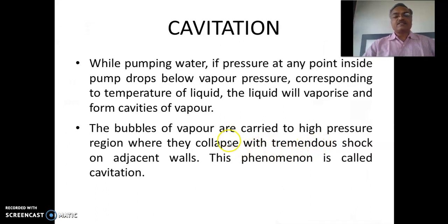Now, what is cavitation? While pumping water, if pressure at any point inside the pump drops below vapor pressure corresponding to temperature of liquid. Temperature is again yet another important parameter here. If it drops below the vapor pressure corresponding to the temperature of liquid, the liquid will vaporize and form cavities of vapor. The bubbles of vapor are carried to high pressure region where they collapse with tremendous shock on adjacent wall. This phenomenon is called cavitation. Cavitation, in other words, is formation of cavity.